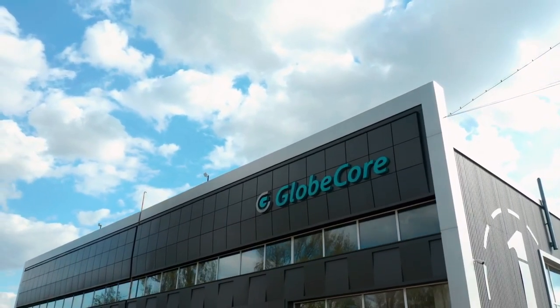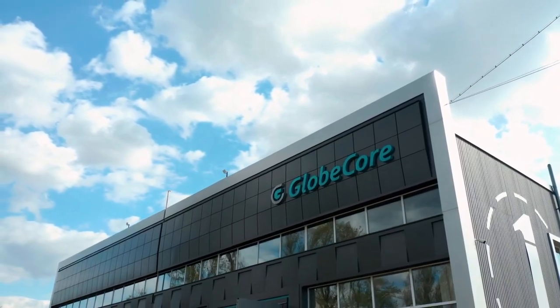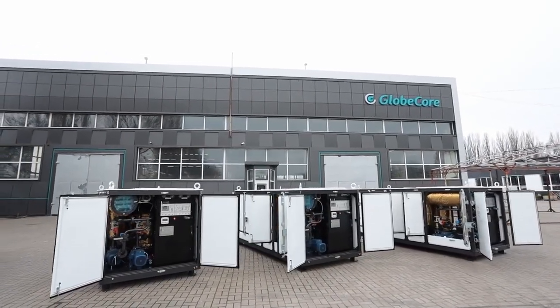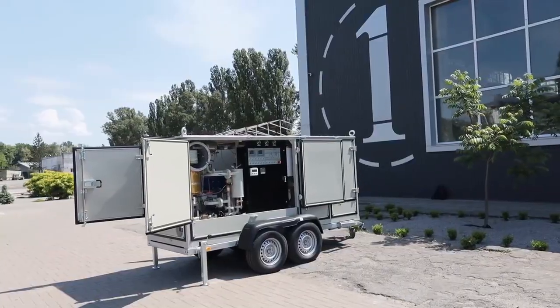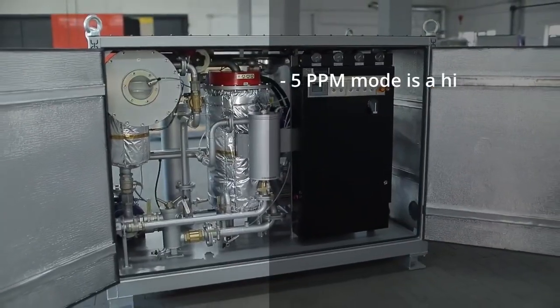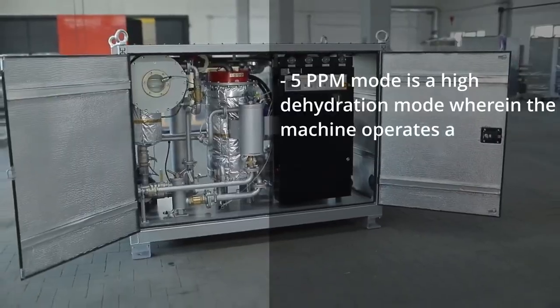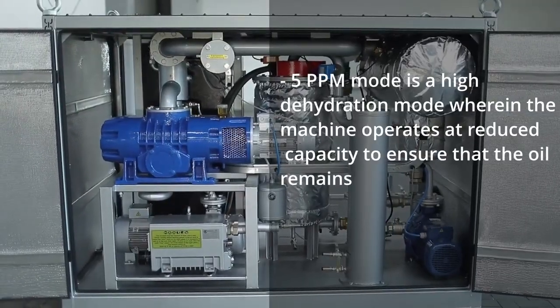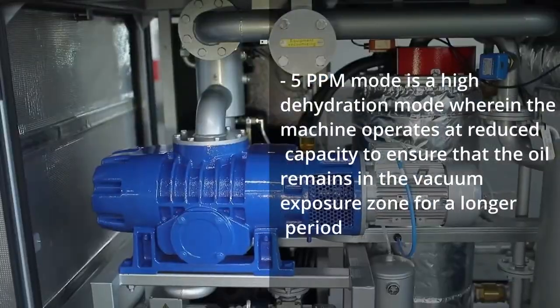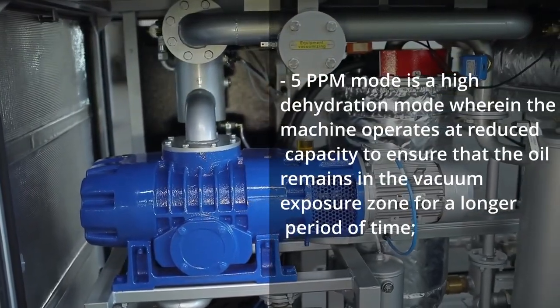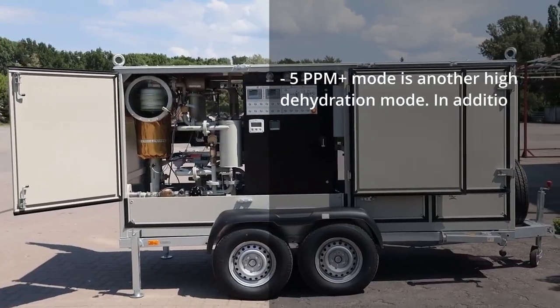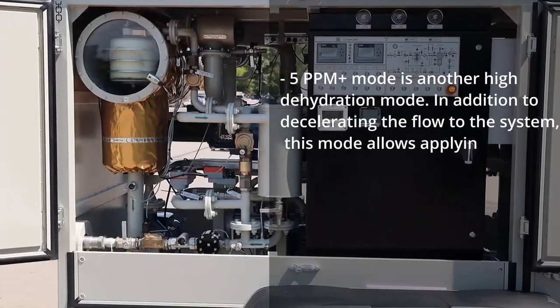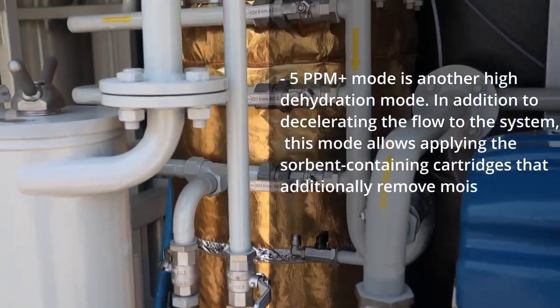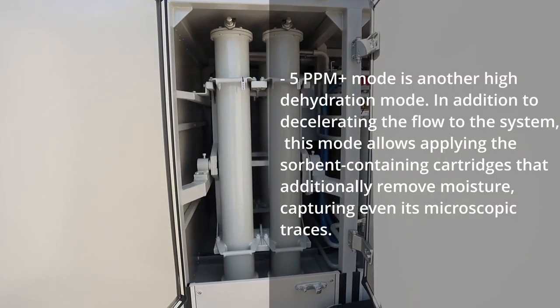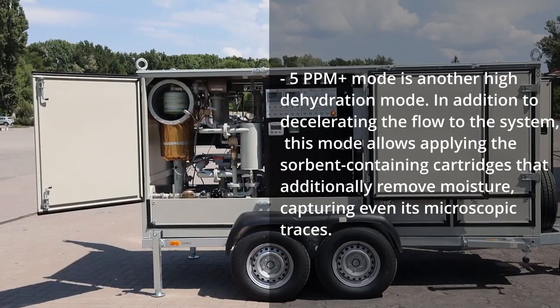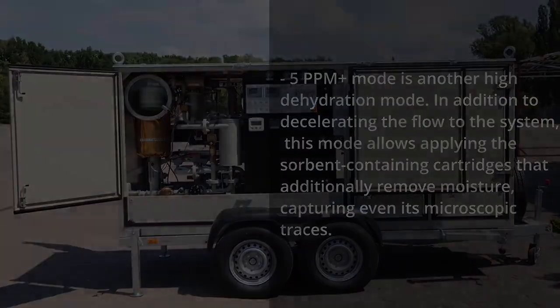Based on customer preferences and requests, GlobeCore has added 2 advanced modes to the standard operating mode of CMM thermal vacuum dehydration machines. 5 ppm mode is a high dehydration mode wherein the machine operates at reduced capacity to ensure that the oil remains in the vacuum exposure zone for a longer period of time. 5 ppm plus mode is another high dehydration mode. In addition to decelerating the flow to the system, this mode allows applying the sorbent-containing cartridges that additionally remove moisture, capturing even its microscopic traces.